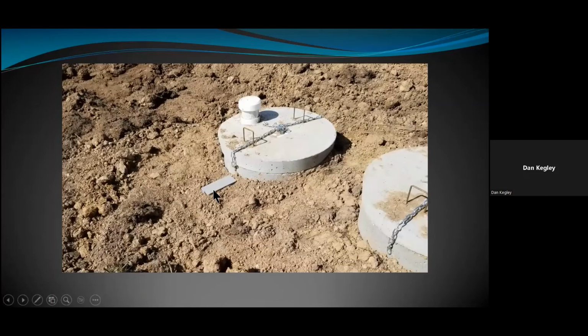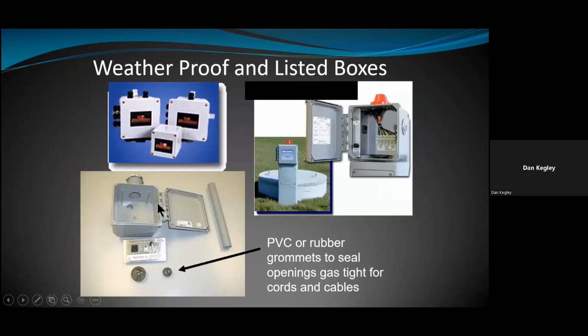So this is an example. It looks like they had an LB. Looks like somebody tried to use an LB conduit fitting, conduit body. Conduit bodies are not acceptable, like a 2-inch or 2.5-inch conduit body, LB, and those kinds of things. They don't have enough capacity. When you go back into this junction box here, you can see how much capacity is in here for putting this circuit, this plate here for the receptacle and those kinds of things inside it.